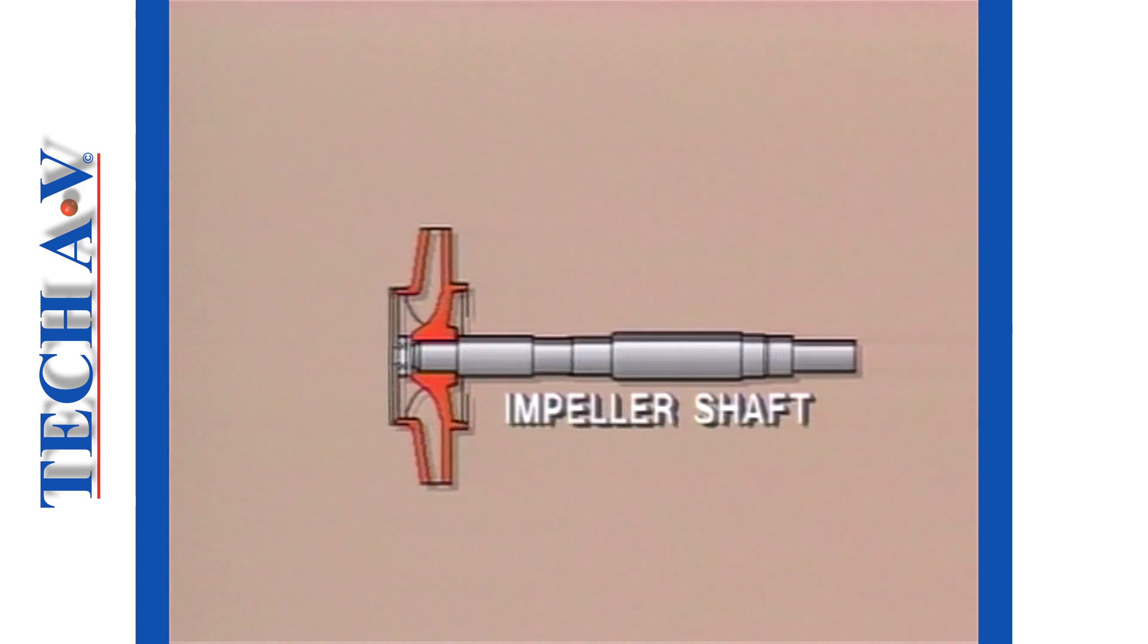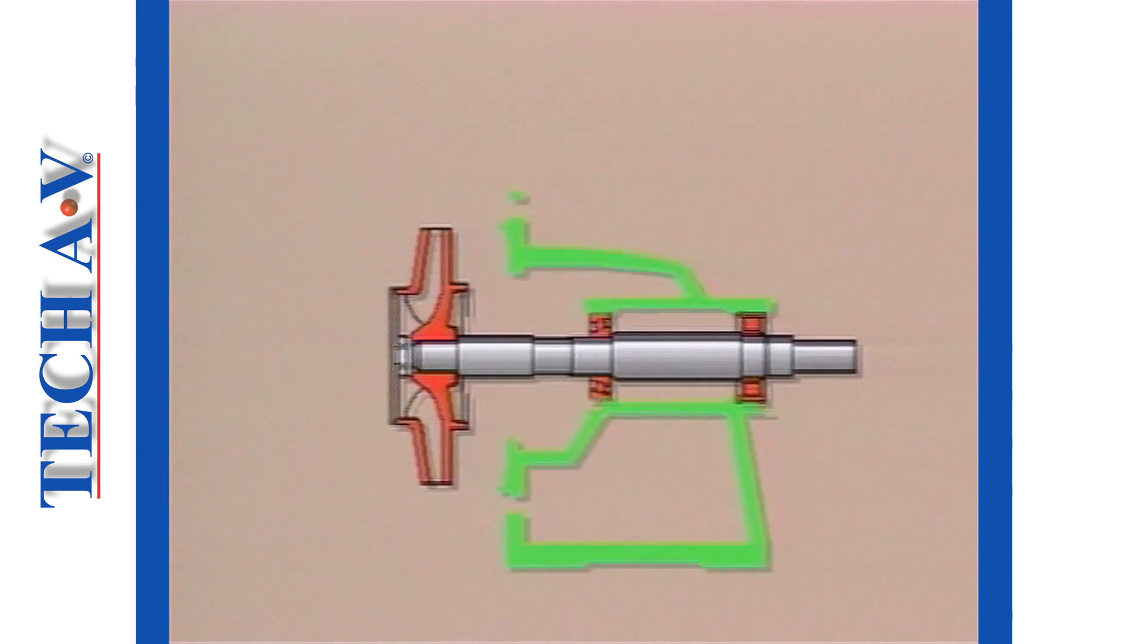The heart of the pump is the impeller, which is fixed to the end of the impeller shaft. The impeller shaft is supported in this unit by ball bearings, although roller and plain bearings can also be used. The bearings and shaft are housed in a bearing bracket.